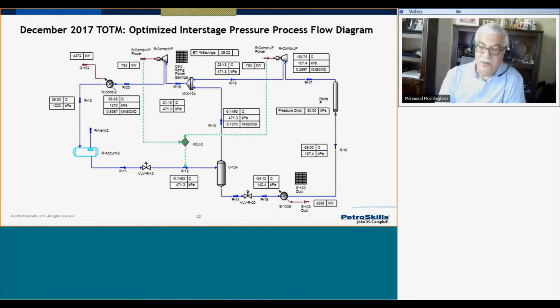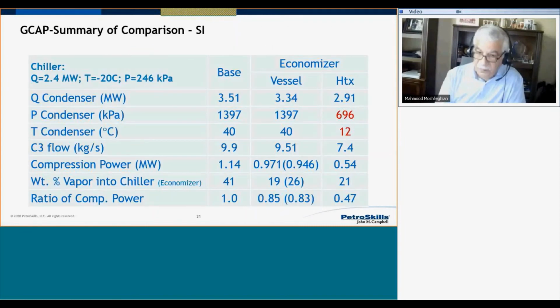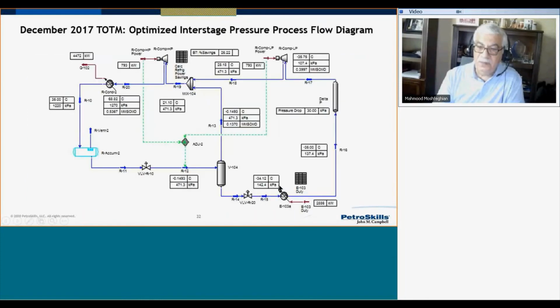So to summarize here, by using a simple refrigeration system, but instead of using air or water as a cooling media, I use a cool process gas, we get lots of saving, and the power reduction is drastic. Or if you go to a mechanical refrigeration system with one flash tank and 2 stages of compression, again, we gain some saving on compression power requirement as well. Of course, the approach temperature plays an important role as well.